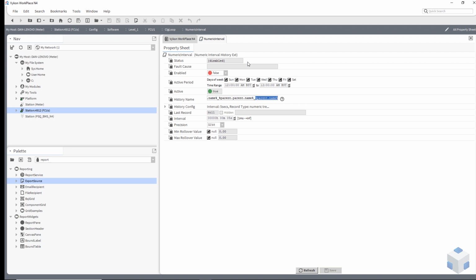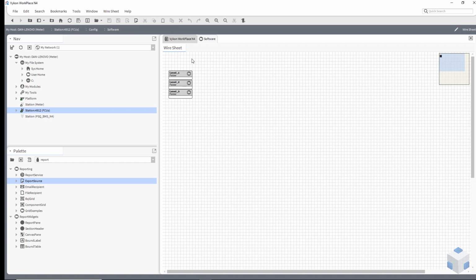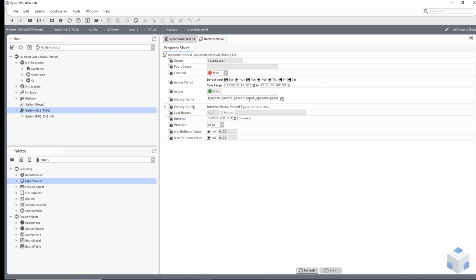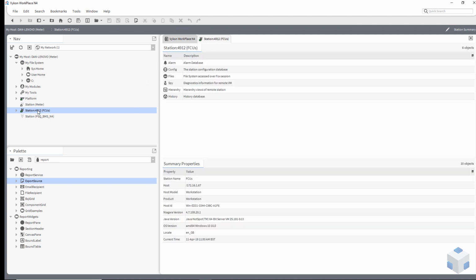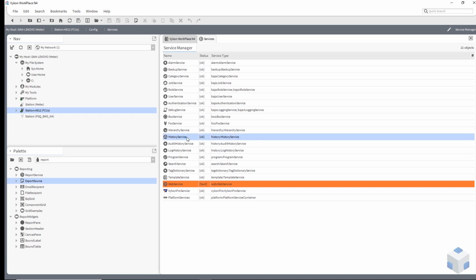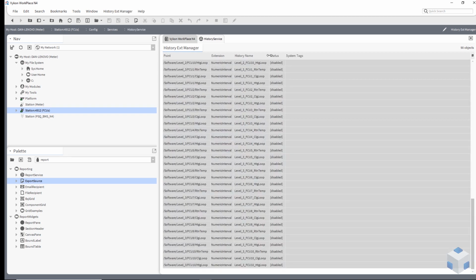It takes a little bit of housekeeping at the beginning, but once that gives us the ability to do that, I can repeat it again and again throughout these floor levels. And again, if I go to here, go into my cooling loop, numeric interval, by using my parent name structure, I can give it level 3, two parents, fan coil unit 10, and again, parent name, heating loop, giving it individuality.